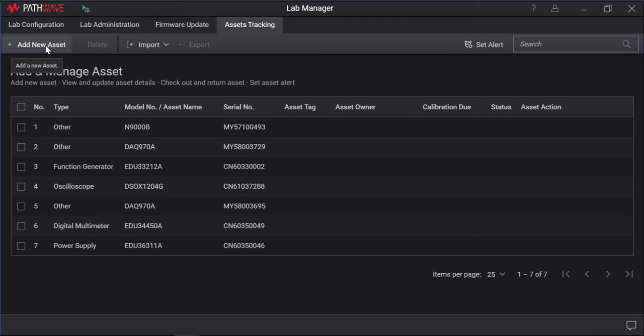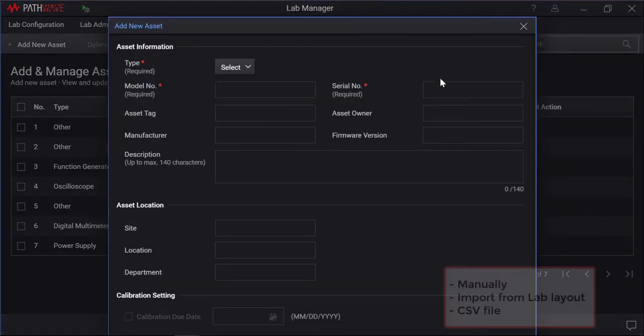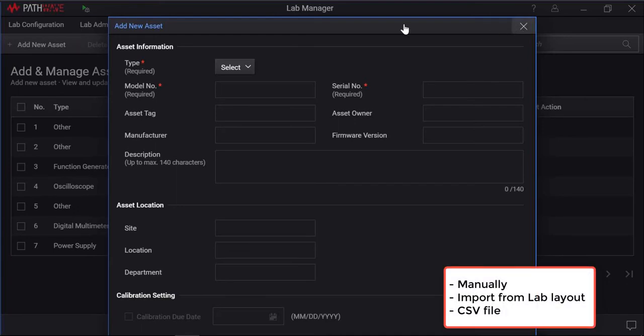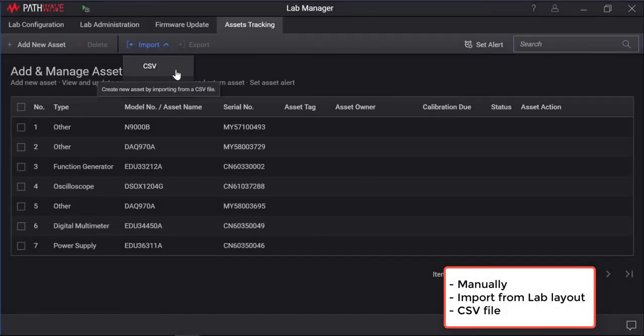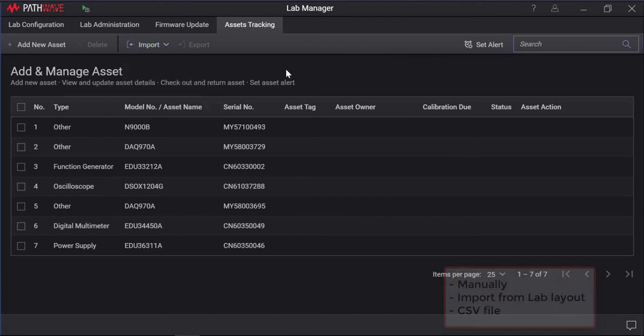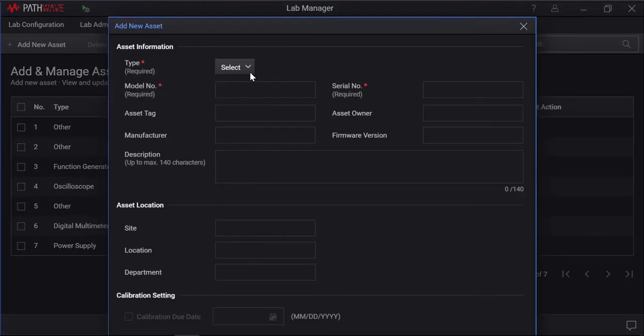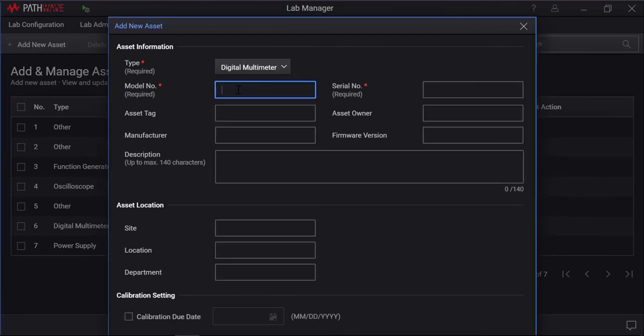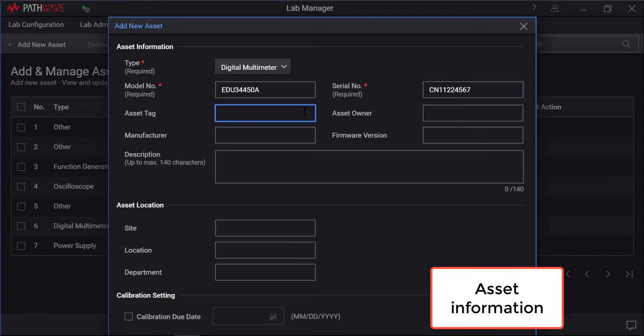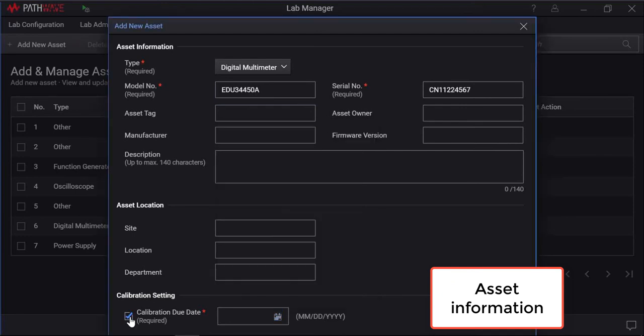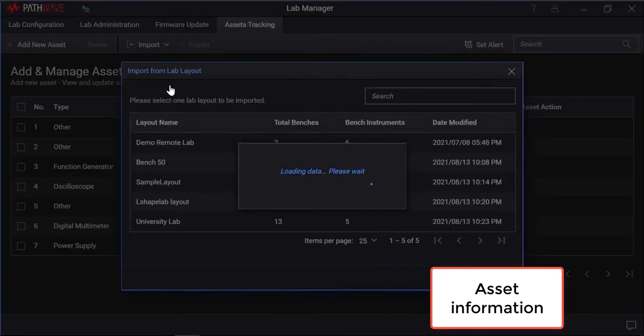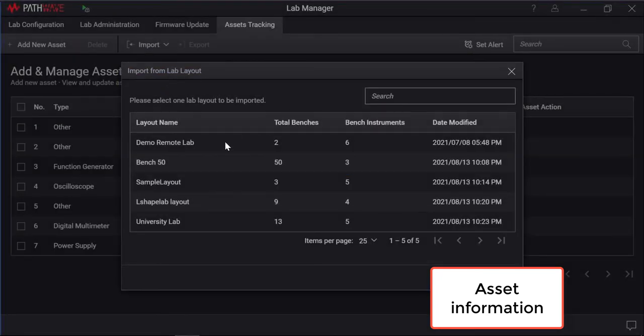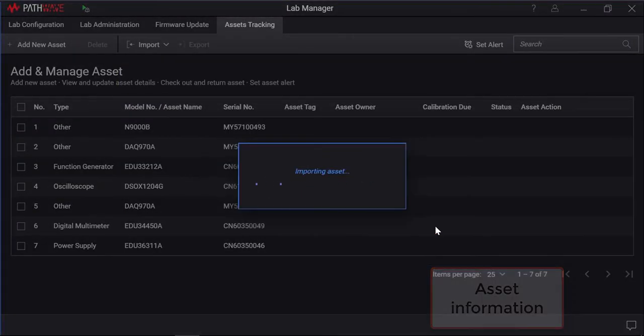Items may be added to the asset tracking list manually, import from lab layout, or from a CSV file. To add a new asset manually, go to the asset tracking tab, and click the add new asset icon. Input all the asset information. You may quickly import all the instruments for the lab layout previously configured into the asset tracking list as well. Click import to add all the configured instruments from the selected lab layout.